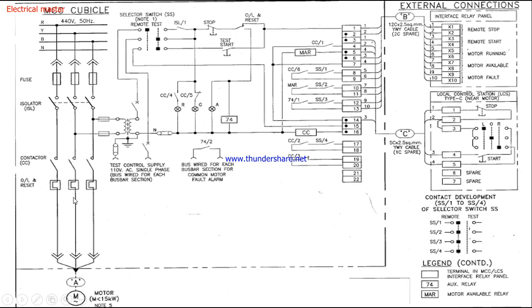From the power circuit we take two wires — R and Y, or R and B — through control fuses and connect them to the control transformer. I am using a single-phase control transformer, so two phases are connected here. From the secondary side we step down from 440 volt to 110 volt.